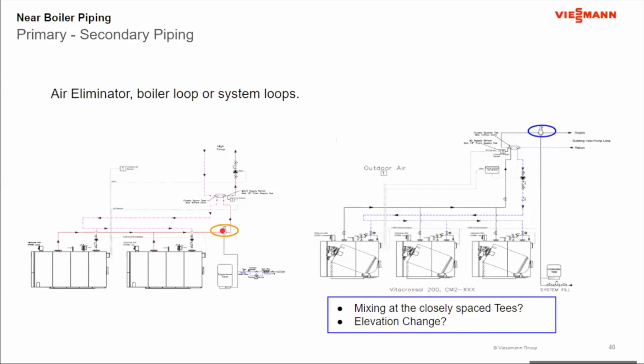If I put this here, I know that it's going to be at the highest temperature. And here it's showing tied into the point of no pressure change with the pumps pumping away. I know that it's at a good pressure point. So for a default position based on temperature and pressure, that becomes a great option, okay? If I put it out here, then it becomes variable. There's a lot of variables that play into it.